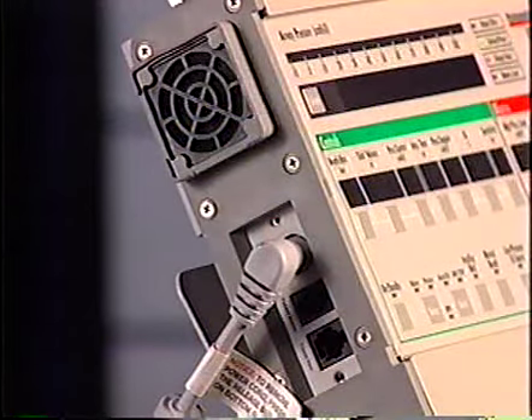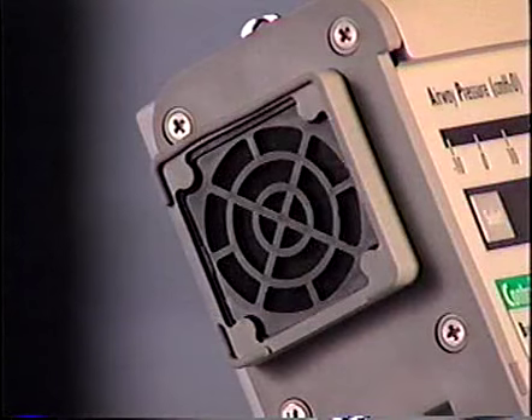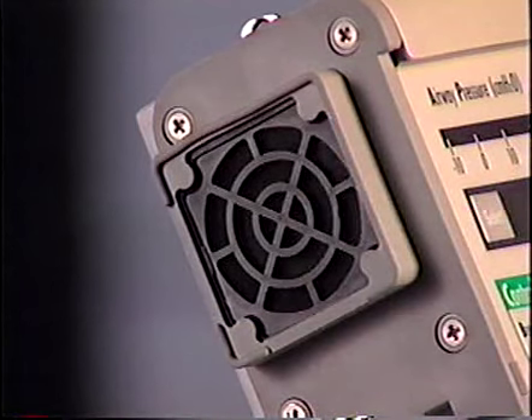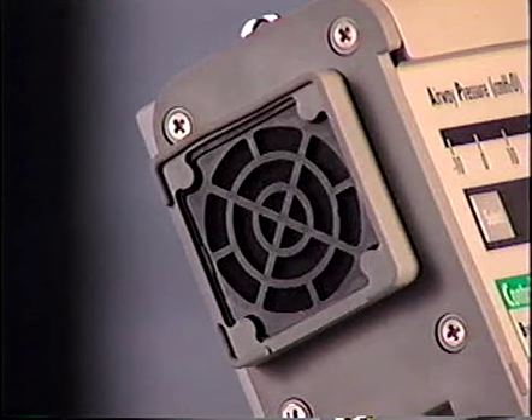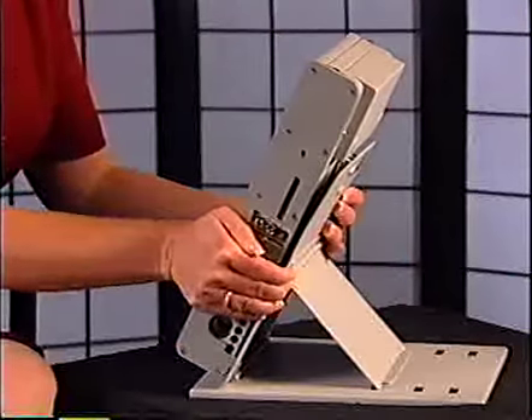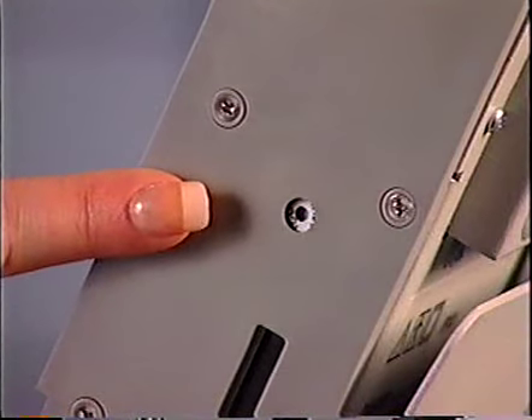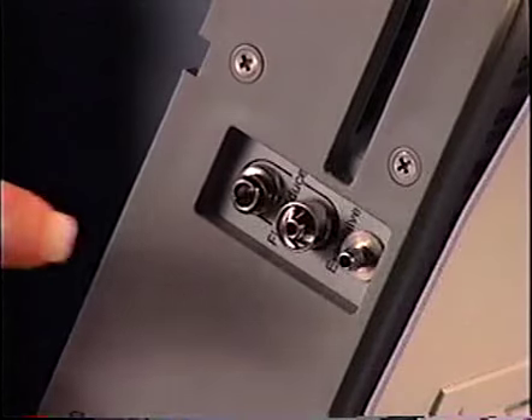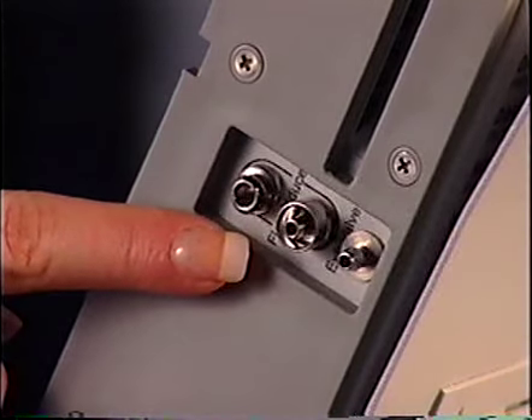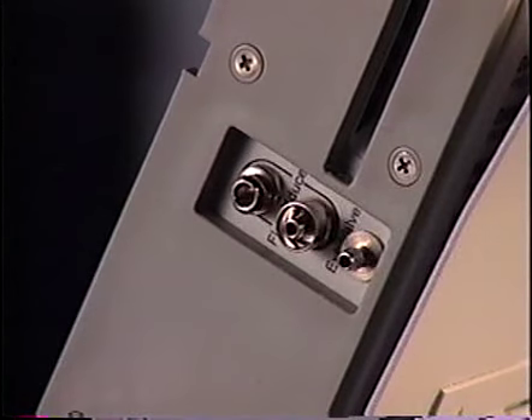Above the ports is the cooling fan. It is important not to block the fan since it is where the ventilator draws in room air. On the right side of the ventilator, we find the opening for the audible alarm. It is important not to block this opening since the alarm volume would be reduced. Next, you can see three small ports. These are for connecting the exhalation drive line and the two flow transducer sense lines.